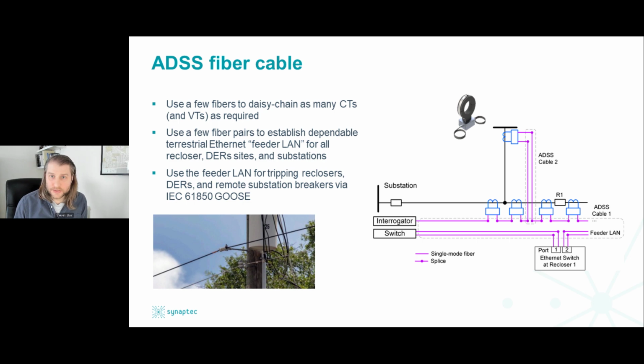So the way that we would suggest deploying this is that the fiber can effectively loop around all of the essential points on the feeder or the circuit, such as recloser locations, any teed lines, and DER connection points. And then sensors can be readily deployed at these locations as required. So typically that will be CTs for protection, but it could be VTs and other types of sensors too. And another benefit is the operators can also use the same fiber for other applications too. Typically ADSS fiber will have multiple bundles available. So there'll be lots of fibers that can be used, and other features can be enabled, such as operating reclosers, transferring intertrips, and it can even be leased for other services.